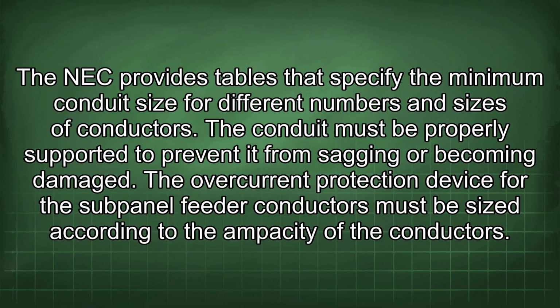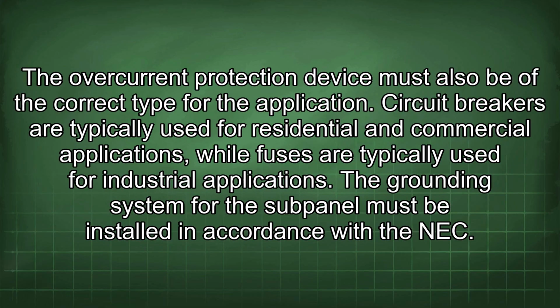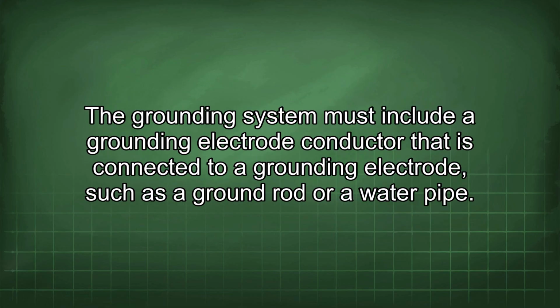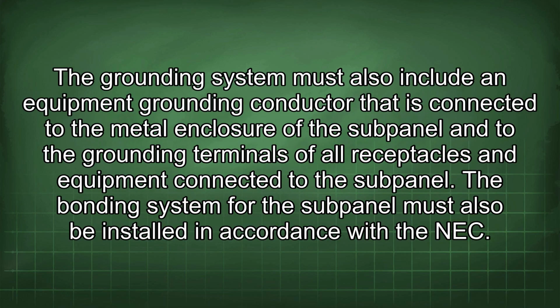The overcurrent protection device for the subpanel feeder conductors must be sized according to the ampacity of the conductors. The overcurrent protection device must also be of the correct type for the application. Circuit breakers are typically used for residential and commercial applications, while fuses are typically used for industrial applications. The grounding system for the subpanel must be installed in accordance with the NEC. The grounding system must include a grounding electrode conductor that is connected to a grounding electrode, such as a ground rod or a water pipe. The grounding system must also include an equipment grounding conductor that is connected to the metal enclosure of the subpanel and to the grounding terminals of all receptacles and equipment connected to the subpanel.